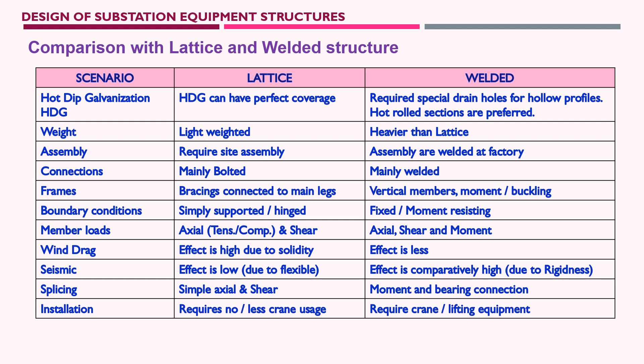For connections, lattice support structures use mainly bolted connections. Welded support structures use mainly welded connections, though some fixing points — such as earthing box, operation box, or tie members — require bolted connections. The base plate in a lattice structure is connected to the angle member with some welding. So we say 'mainly bolted' for lattice and 'mainly welded' for welded structures, rather than wholly one or the other.